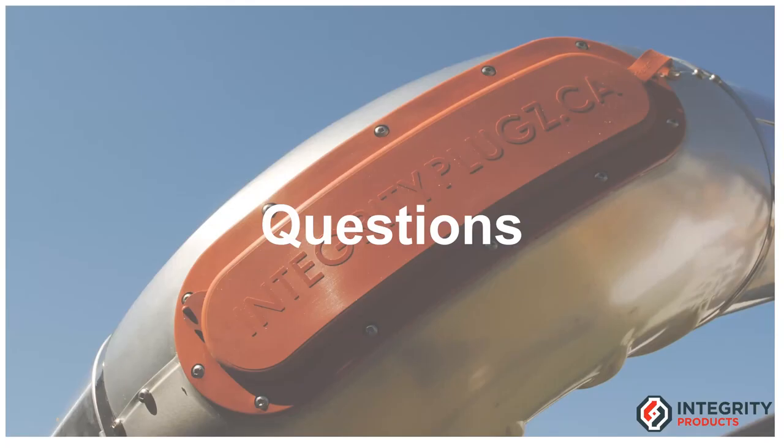Yeah, well, coating is known to be a very good last line of defense, but even with the coating, we cannot undermine the importance of contact-free systems. Even with coatings, we have to have a contact-free system so that the soaked insulation can be kept away from the coating. Yeah, you still don't want soaked insulation in direct contact with your coating system. Absolutely. Also, there is a variety of coatings available for a variety of materials. But the key benefit with the PTFE, I see, is that it can suit a variety of materials regardless of their metallurgy. So carbon steel, alloy steel, stainless steel, whatever we have, and for a range of temperatures up to 260 degrees Celsius, it can be retrofitted for those applications.